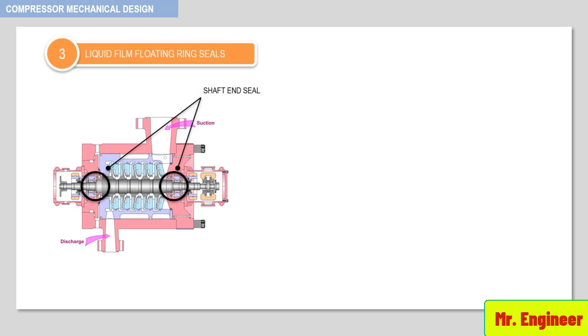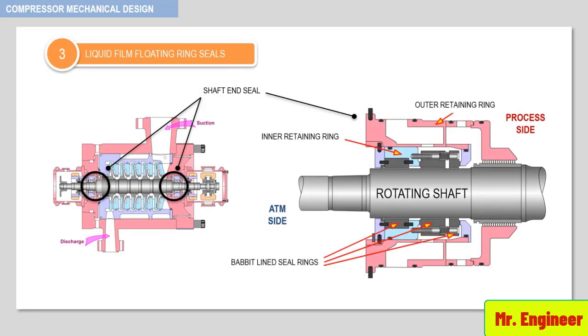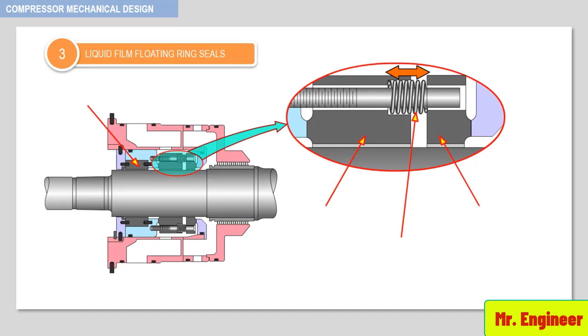The figure depicted here shows a standard liquid film floating ring seal. The seal assembly consists of a seal cartridge to which are fitted three babbitt-lined seal rings and a retaining ring. The cartridge is retained by means of an outer retaining ring. The three babbitt-lined seal rings are namely the inner seal ring, the outer seal ring, and the restriction seal ring.